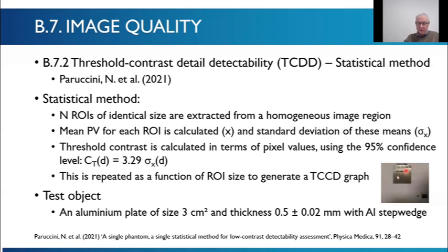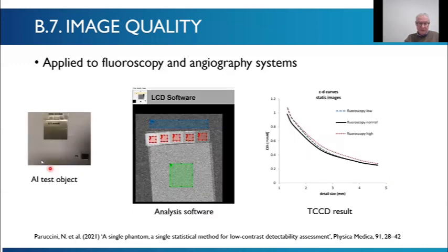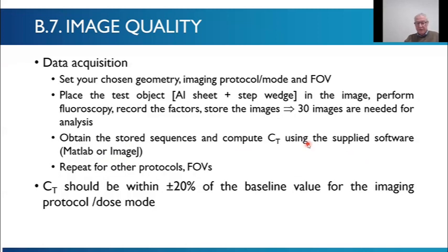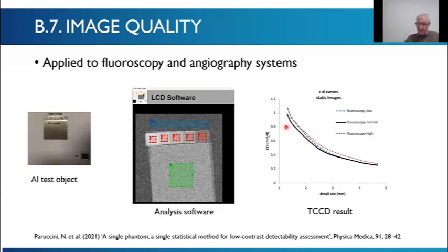region here. I think we see it next. Here's your image of this. You extract ROIs of different sizes in here. You use the measured pixel values in the step wedge to convert to an aluminium equivalence, and then you can calculate a contrast detail curve for different fluoroscopy modes, for example. This uses fewer images than the SNR squared method, but it's basically just using the noise in the image. You can see that there's no target here.